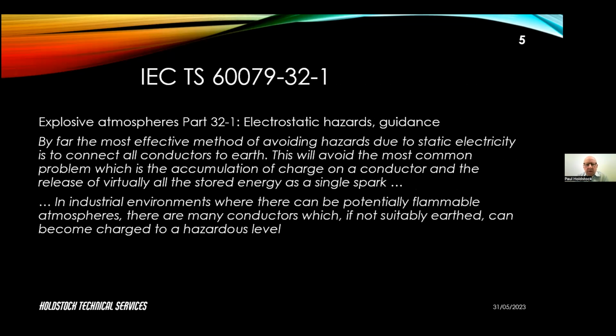So what do standards tell us about earthing and the need for earthing? Well, if we look at the IEC international standard, it's actually a technical specification, but that's really just a standardization term. It's a standard 60079-32-1. It's a standard for explosive atmospheres and specifically on dealing with electrostatic hazards within those atmospheres. And what it says in terms of earthing is that by far the most effective method of avoiding hazards due to static electricity is to connect all conductors to earth. And this will avoid the most common problem, which is the accumulation of charge on a conductor and the release of virtually all the stored energy as a single spark.